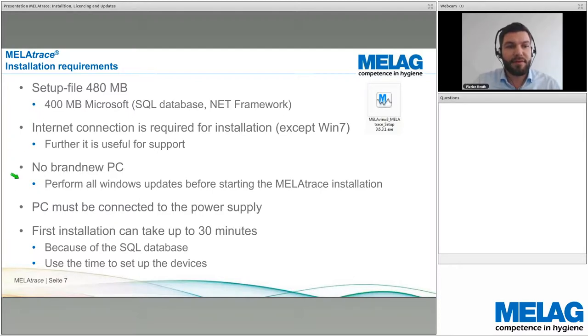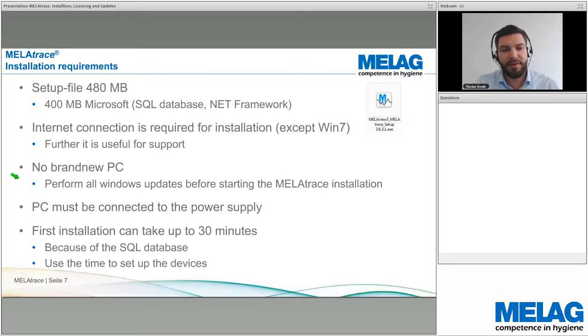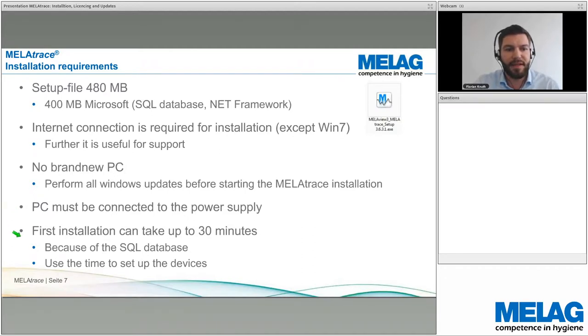If you have a new PC, be aware that on the first internet connection, it will try to download all pending Windows updates. You cannot install MelaTrace at the same time as Windows updates, so it will take a very long time. Best practice: make the PC ready by completing all Windows updates first, then install MelaTrace. The PC must stay connected to power, and the first installation can take up to 30 minutes because of the SQL database — use that time to set up device connections.